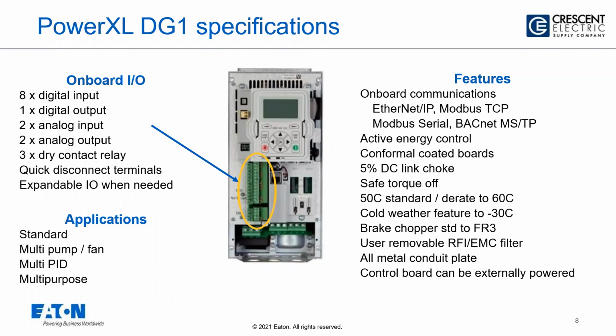But then we have this wonderful application called multi-pump, multi-fan, where now I can stick multiple of these drives, tie them all together, have them all run pumps or fans, and then I can do lead lag with pressure control and some really neat features with that. It does have a PID, actually has 2 PID loops in it. And then we have one where you just take the gloves off and we give you access to all 900 parameters and it's just completely configurable.